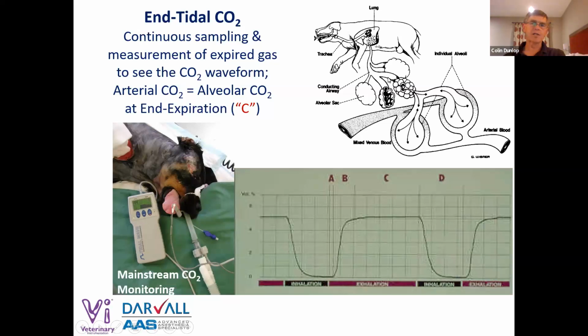Then we've got this gas down here in the conducting airways, down in the bronchi and things, which is a bit of mixed gas, some CO2 in it. And finally, we get the alveolar gas. And we look at that waveform. It starts at 0, inspiration, the first third of expiration, which is the gas that never made it to the lungs, so it's still room air or inspired anesthetic gas. Then a rising CO2, those distal airways, and then that tall, flat part of the curve, which is the alveolar gas. And that's the gas we're interested in reading, the end-tidal CO2.